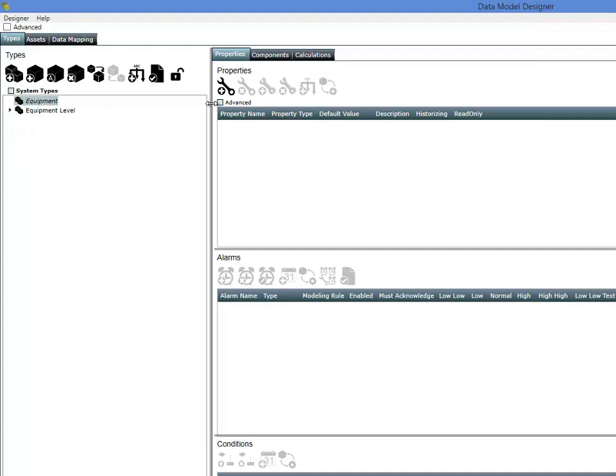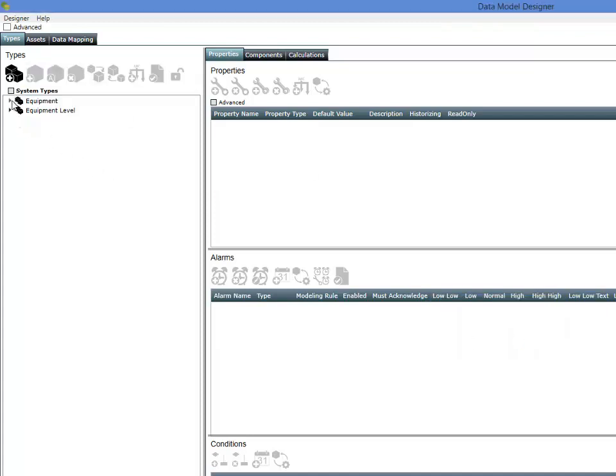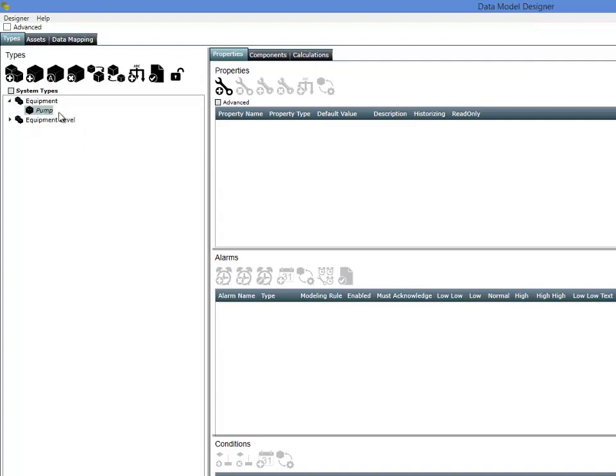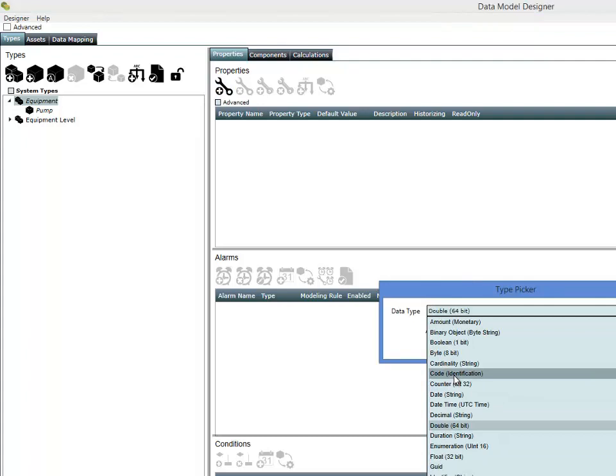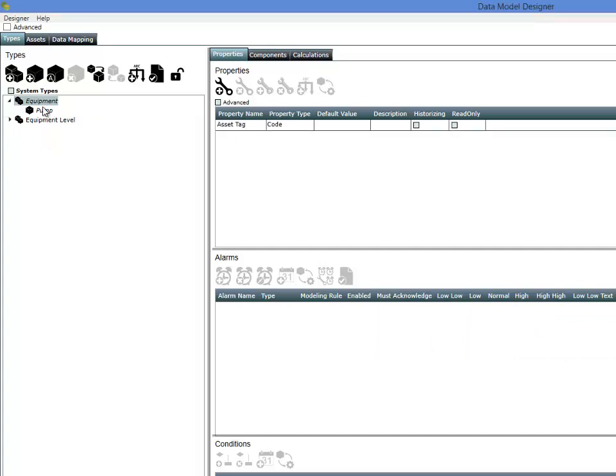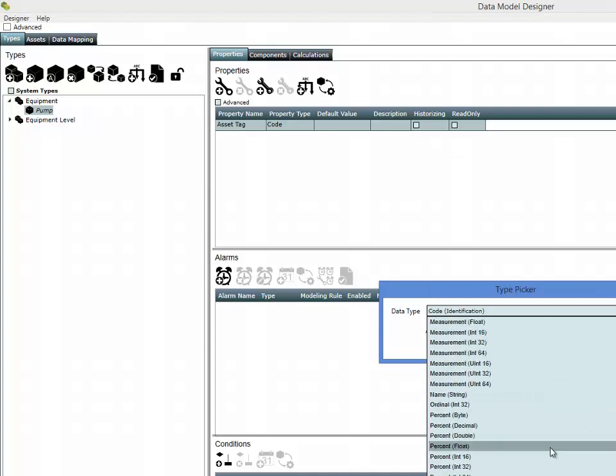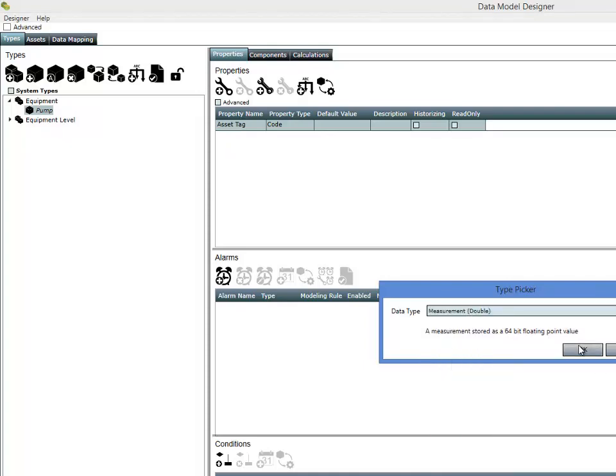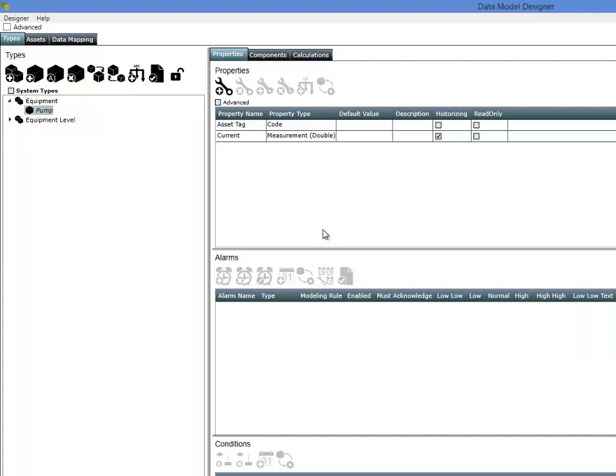We've got a couple of types here in a new solution, mostly empty. Going under Equipment, we're going to start by creating a new type — we're going to create a Pump. Everything within the system has inheritance, so if I go to the Equipment type I can add a new property, maybe an asset tag, and any type of equipment created underneath Equipment — the Pump for example — is going to inherit that asset tag property. Going to the Pump, I'm going to add a couple of properties: measurements with a data type of double. For the pump, we may want the current (how much electricity the pump is drawing) and the flow rate.